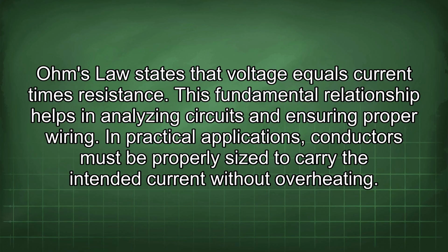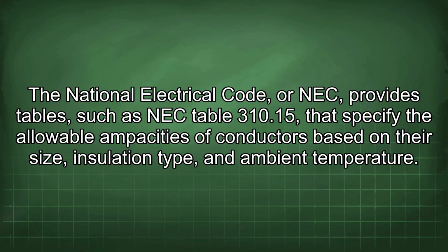In practical applications, conductors must be properly sized to carry the intended current without overheating. The National Electrical Code, or NEC, provides tables such as NEC Table 310.15 that specify the allowable ampacities of conductors based on their size, insulation type, and ambient temperature.